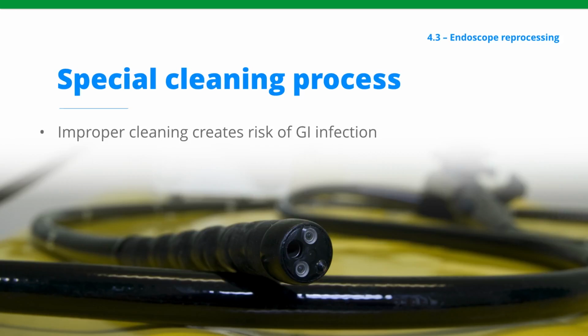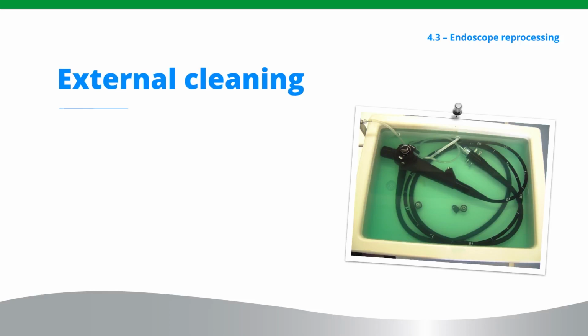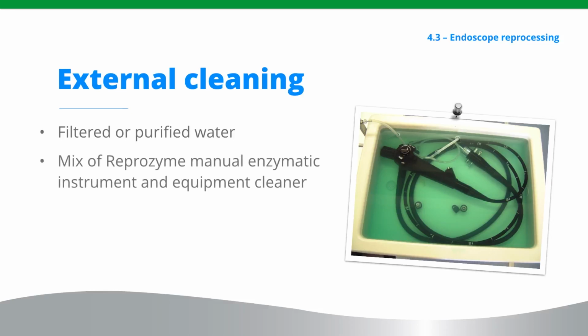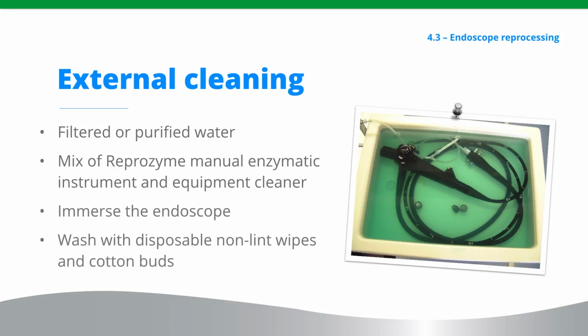Flexible endoscopes present special risks of damage if submitted to heat sterilization. The lens areas are particularly vulnerable. The repair bill for a heat-damaged scope can be so expensive that the risk is not worth it. Cold sterilization is therefore recommended. Start with a large bowl of filtered or purified water with a mix of Reprozyme manual enzymatic instrument and equipment cleaner. Immerse the endoscope completely. Wash in detail with disposable, non-lint wipes and cotton buds.